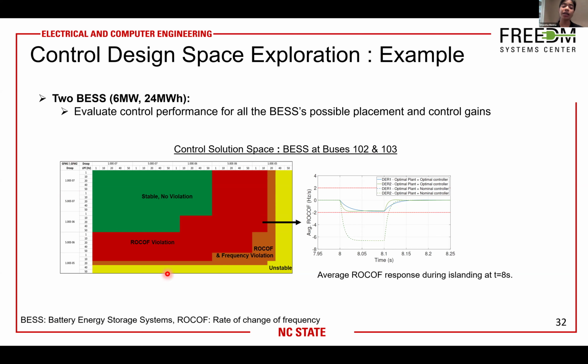Our evaluation can separate this region into stable areas, unstable areas, and identify which regions will have violations with the IEEE 1547 standard, like rate-of-change-of-frequency (ROCOF) and frequency violations. We can see that if any random controller gain, like the standard 5% droop with LPF, is selected, it can still have a ROCOF violation.